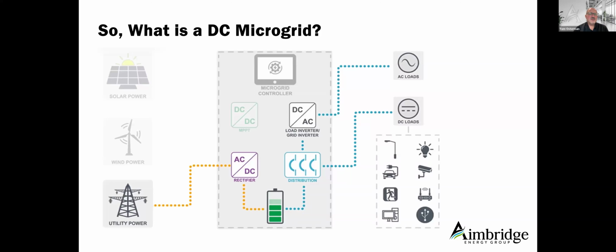The next slide shows an interesting alternate power flow configuration: utility power feeding the microgrid system and adding in battery recharge. If you have no solar, no wind, no renewable generation, or the system's down for maintenance or has a fault, we have a bypass capability where AC power from the utility feeds a rectifier, which converts it to DC, charges the battery system back up, and continues to support our AC and DC loads. It's important to note that's a bypass, where the utility is our backup system now instead of being our primary source.